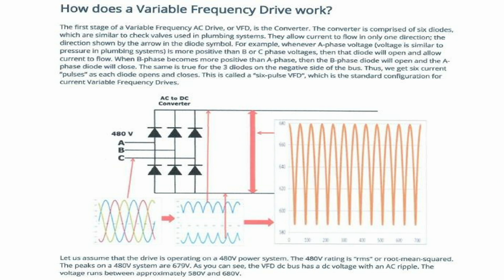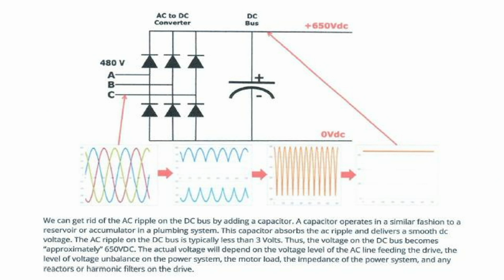And down here at the bottom, the peak on a 480-volt bus is 679 volts. I think that's what we ran as far as calculations go. And that develops the voltage needed for the DC bus. And then the capacitor comes along, and boom. Downstream of the capacitor is our DC bus, 650 volts DC, and it looks like that. The input looks like this, goes to the diodes, puts out this ripple effect, and this is on the positive side. There is no negative here. These are all positive ripples. Zero line would be right below that. There's nothing down here. So here we go with this ripple, hits the capacitor, and puts out a flat line DC signal that enters the engine section.